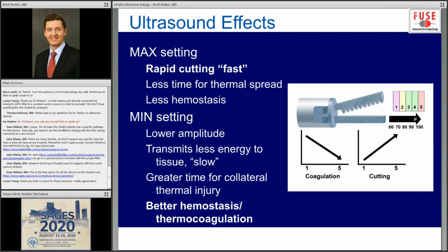So now we're going to spend some time to go over how the device is used and some of the caveats and techniques that can be used inside the operating room to use it effectively. So in general, there are two main settings on the ultrasonic shear. This has to do with the amount of protrusion or length of oscillation of the straight jaw. So the longer the blade excursion, the more mechanical energy is transmitted to the tissue. And this results in a greater cutting efficiency.